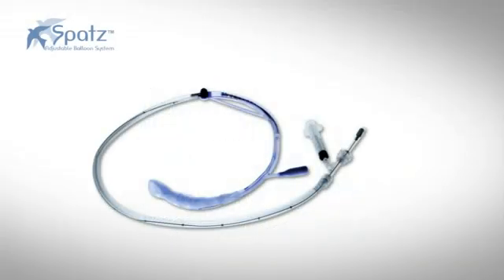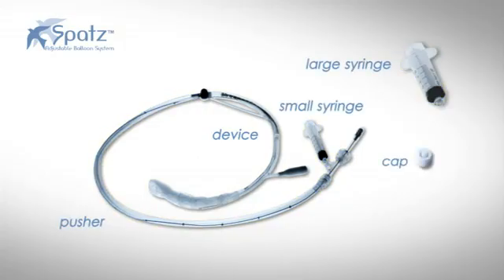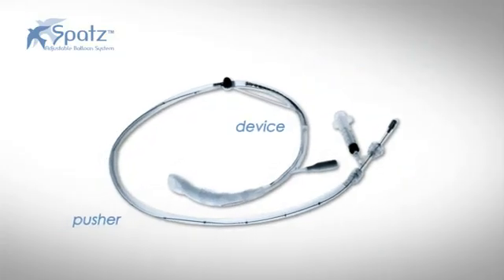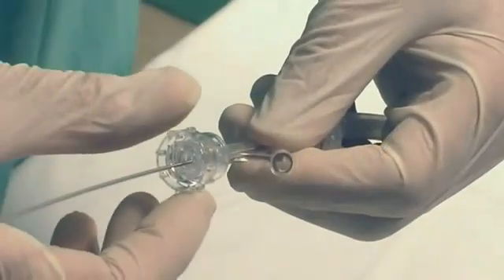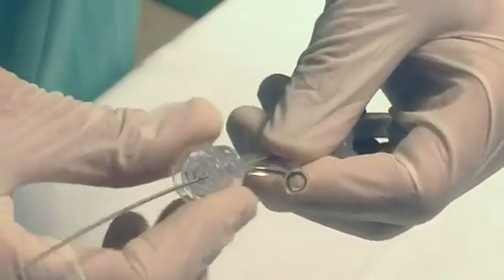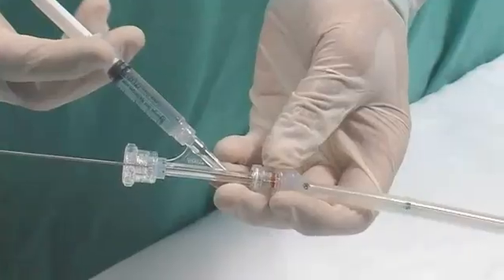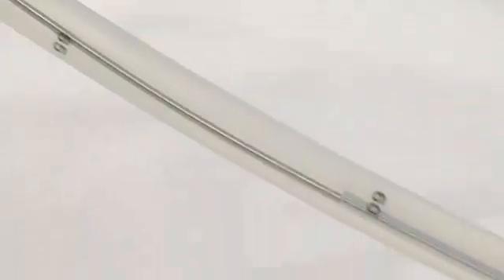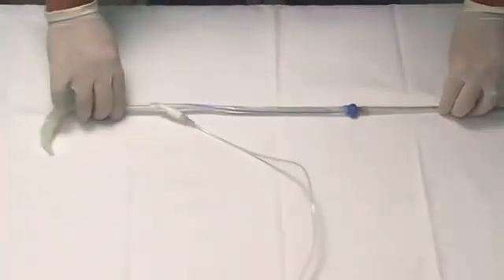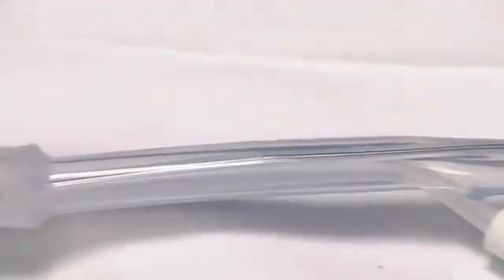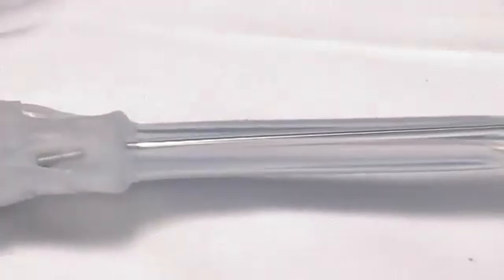The insertion kit contains the device connected to the pusher with its Y port and wheel, 2 syringes, a cap, and mineral oil. The insertion assembly consists of a guide wire that passes through a pushing catheter and the device. The wheel should be in the closed position, clockwise. Lubricate the lumen with the provided oil. Straighten the catheter curls and advance the guide wire until it enters 1 centimeter into the balloon.